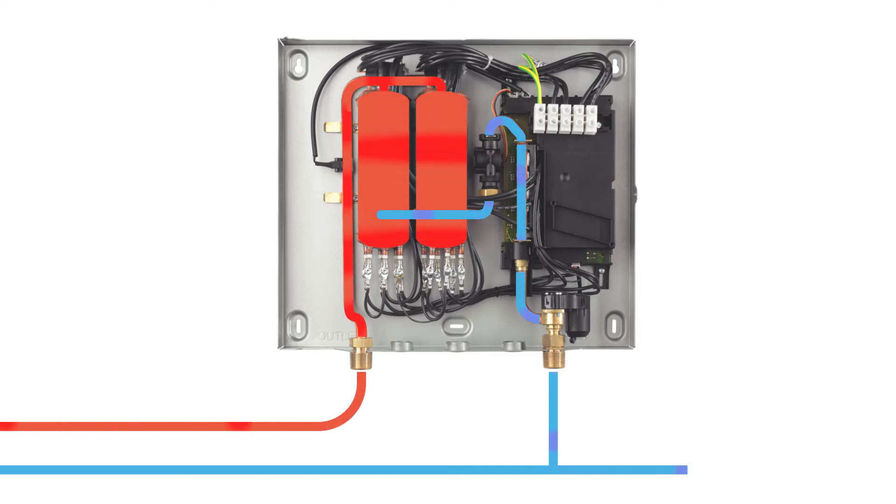This means that there are two things to consider when choosing which model or size of tankless water heater is needed. First is the amount of water that needs to be heated as it passes through the water heater. This is the flow rate. Second is how hot the tankless water heater needs to heat the water. This is the temperature rise, the difference between the temperature of the incoming cold water and the outgoing hot water.